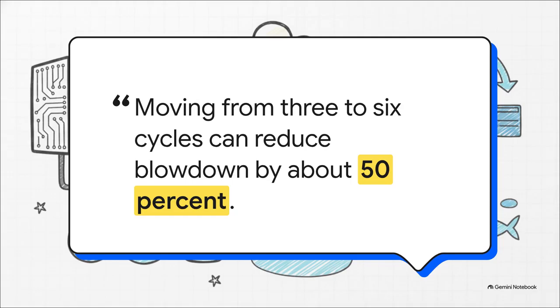Moving from 3 to 6 cycles saves about 20% on makeup water, the fresh water brought in to replace what evaporated, and it cuts your blowdown volume completely in half. But there is a catch: concentrating water saves gallons for sure, but it makes the resulting blowdown chemistry incredibly difficult to manage. It is a constant trade-off between volume and toxicity.